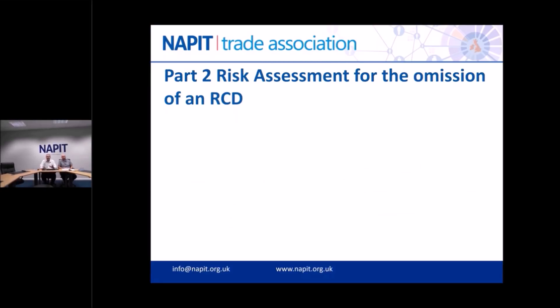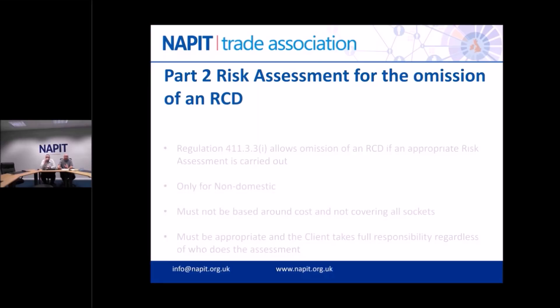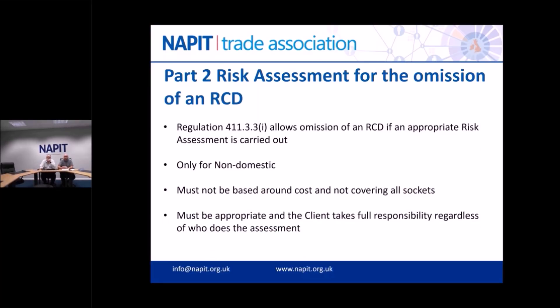Let's look at Regulation 411.3.3 - it allows omission of an RCD if an appropriate risk assessment is carried out, but note that applies to anything other than a dwelling. For a dwelling, any socket outlet requires 30mA RCD protection - there's no question, and we can't even have a specific label anymore in the 18th edition. For other premises, the risk assessment must be carried out with the client, who takes responsibility for it and needs to be aware the assessment may need updating if the building changes its use.